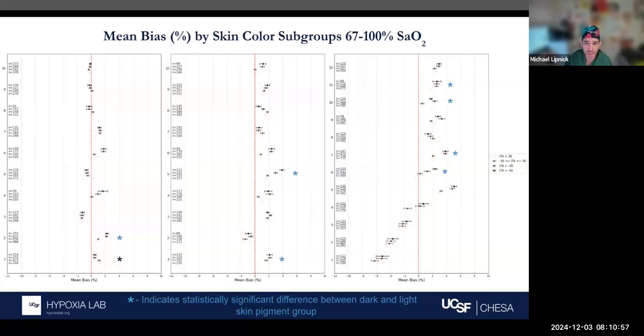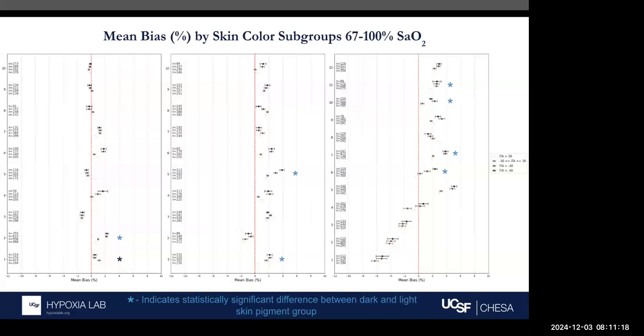Thanks for that comment. So anyways, just making the point that how best to ensure diversity is one thing, but it is relevant for the issue of pulse oximetry, making sure that we're accounting for groups where we are seeing differences in performance in the devices. All of these data are on the OpenOx website if you want to dig into it. And sorry for interrupting, can I just hammer home that there are some devices that perform really well across the different pigmentation groups, and some that have a big disparate response, right?